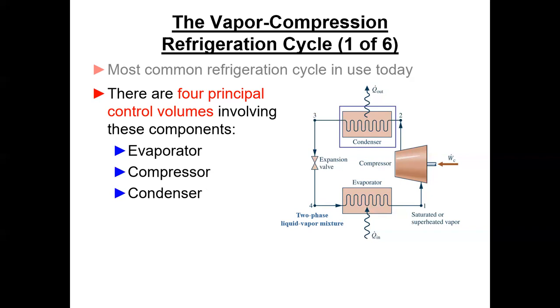The refrigerant goes into the condenser where it condenses. We blow some sort of cooling medium — a lot of times just outside air — and dump the heat to the environment. The refrigerant vapor coming out of the compressor is probably 150 to 200 degrees, so even when it's 95 or 100 outside, we can still transfer heat to that warm outside air. The last component is the expansion valve, basically a throttling process, where the high pressure liquid drops pressure. A little bit flashes to vapor, most stays liquid, and that pressure drop significantly lowers the temperature — probably into the low-to-mid 30s Fahrenheit — then back into the evaporator.